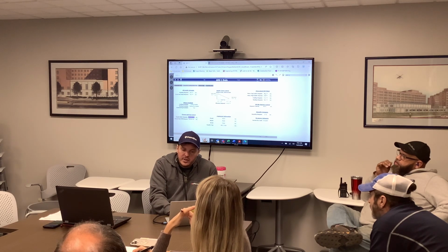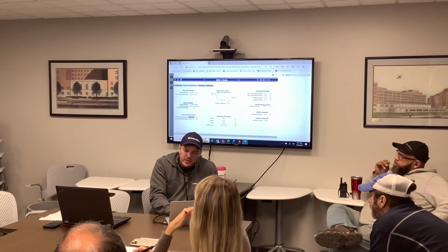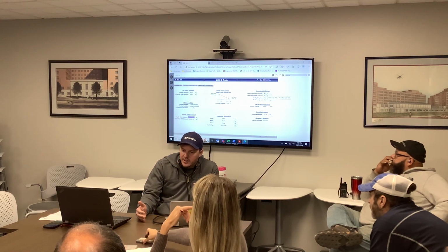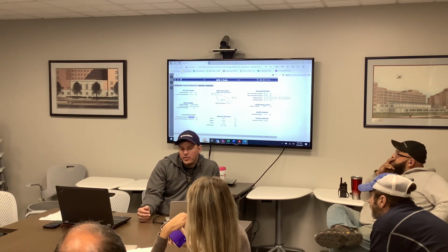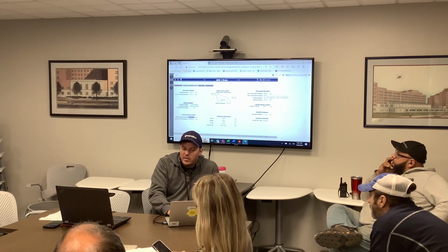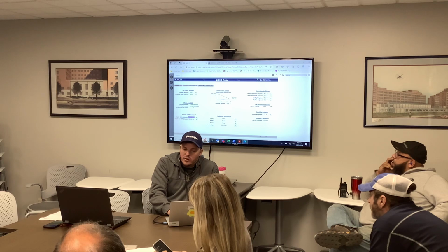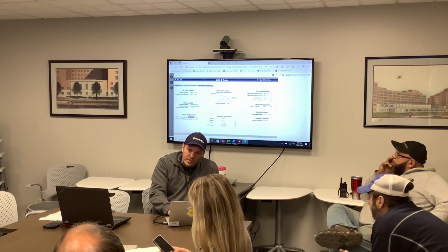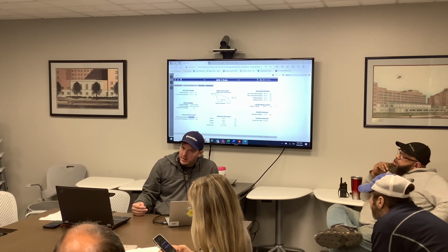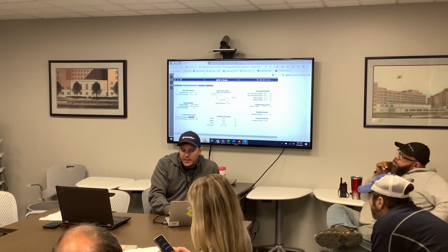Unoccupied cooling set points. So this is actually looking at your zones. This air handler feeds VAVs and airflow valves. So if 3 or more of those spaces, while unoccupied, exceed 80 or drop below 60, the unit's gonna kick on to an occupied mode until those spaces are satisfied. It's 3 or more. Yeah, 3 or more.